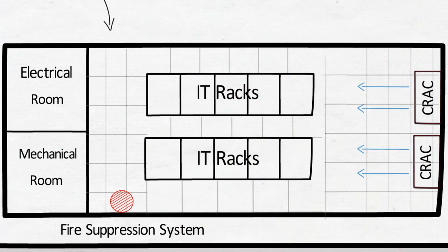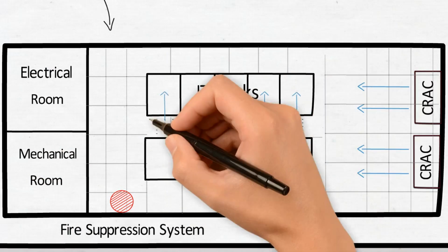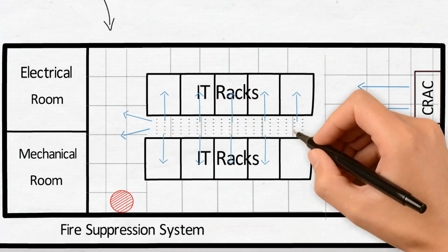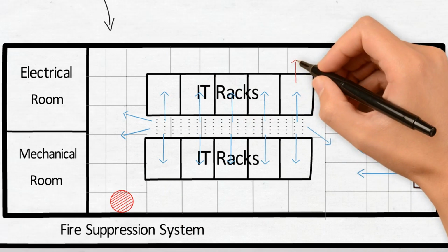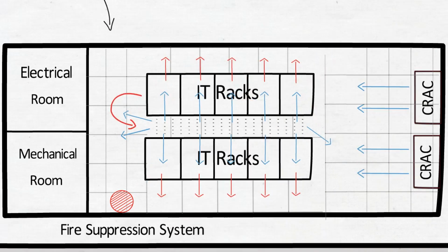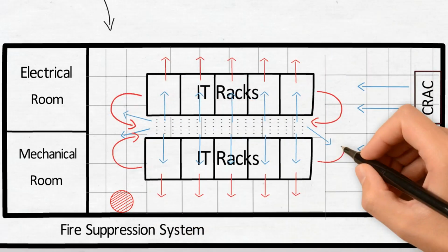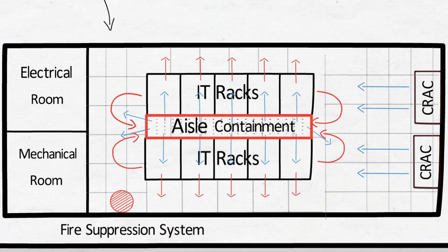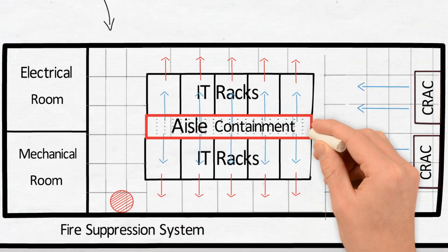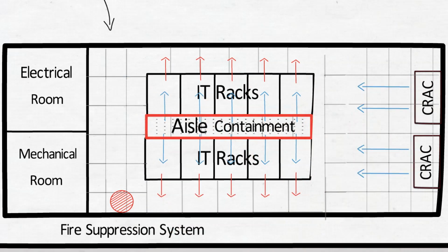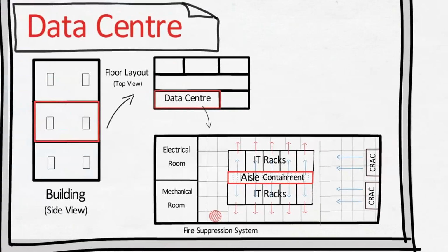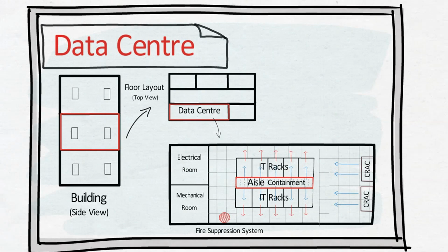This is why our R&D is always working to improve the efficiency of electrical and cooling systems, while enhancing the modularity and availability. One of the most efficient technologies that has been developed is aisle containment. It increases the cooling and the electrical efficiency by avoiding mixing cold air with hot air inside the data center. However, in this case, the hot air is still exhausted to the data center environment, which will raise the temperature in the data center itself.